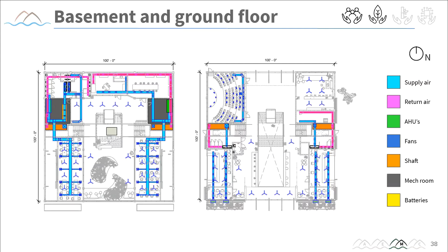The rest of the rooms is supplied by the decentralized air handling units in the facade. This is seen well in the higher stories, where most spaces are connected to the facade ventilation system. The decentralized concept saves a lot of duct meters, which makes the system more efficient, but also more resilient toward technical breakdowns, because the failure of one subsystem does not automatically lead to the failure of the whole.